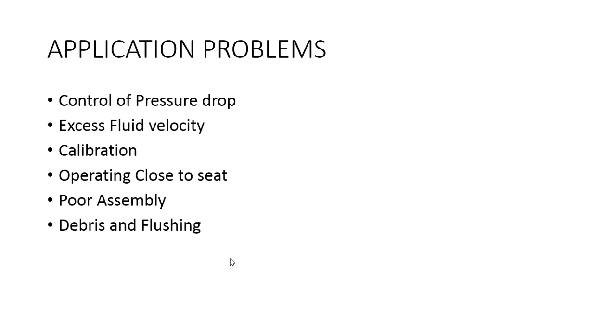Next is the calibration of a control valve. To achieve full seat load and maintain tight shutoff when the valve is closed, the calibration must be done perfectly. Many times it happens that the plug is just positioned at the seat instead of assuring that the closing member is fully loaded against the seat. Hence, if the calibration is not done properly, there could be a chance that the valve will leak. The calibration can be done with the positioner or without the positioner.